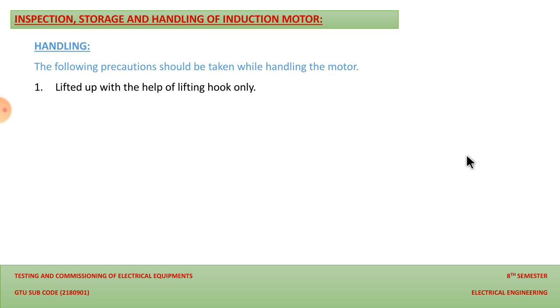Then the extension of the shaft should not be used for dragging the motor. We cannot use the shaft extension to drag the motor, as that can harm the alignment of our machine. Also, the bearing will get worn if we use the shaft extension for dragging.